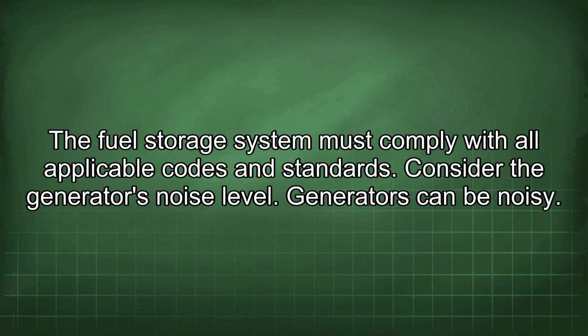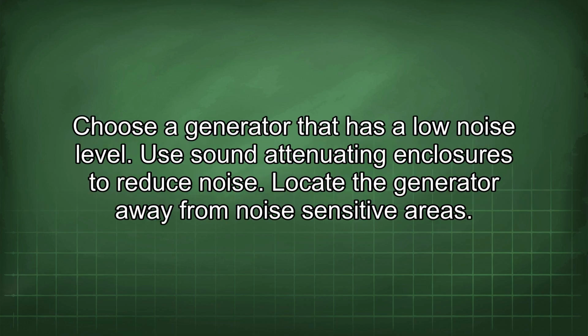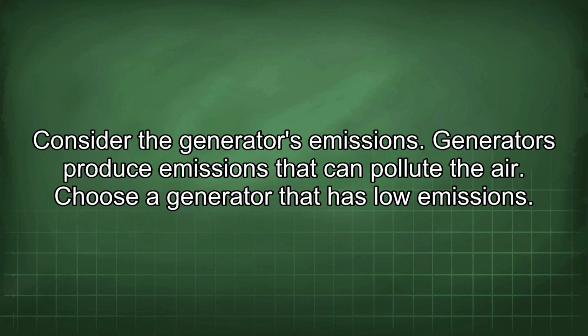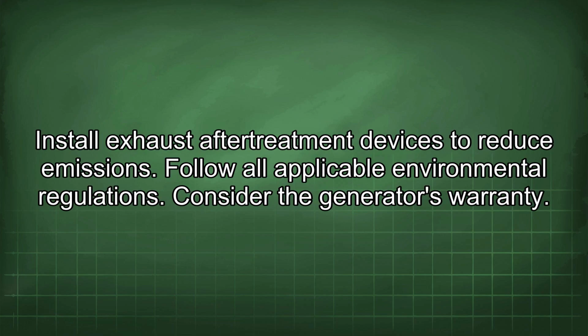Consider the generator's noise level. Generators can be noisy. Choose a generator that has a low noise level. Use sound attenuating enclosures to reduce noise. Locate the generator away from noise-sensitive areas. Consider the generator's emissions. Generators produce emissions that can pollute the air. Choose a generator that has low emissions. Install exhaust after-treatment devices to reduce emissions. Follow all applicable environmental regulations.